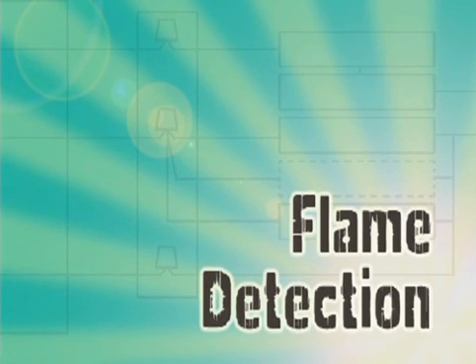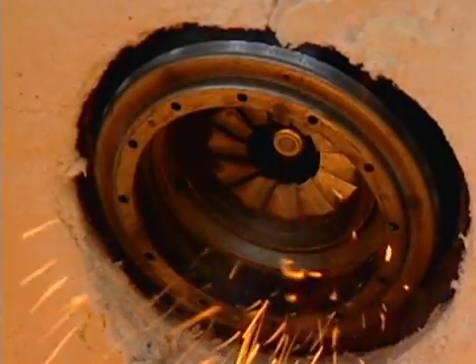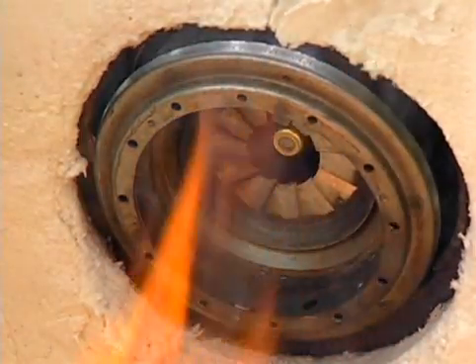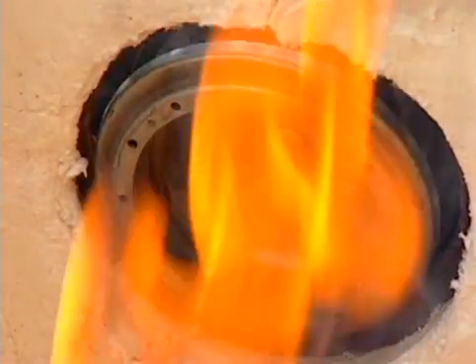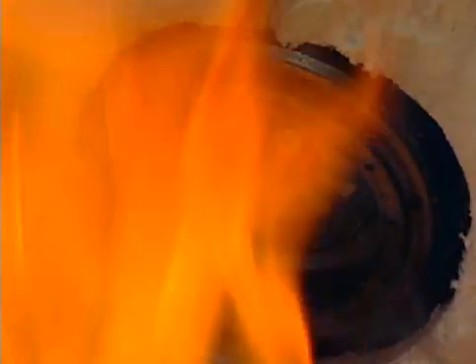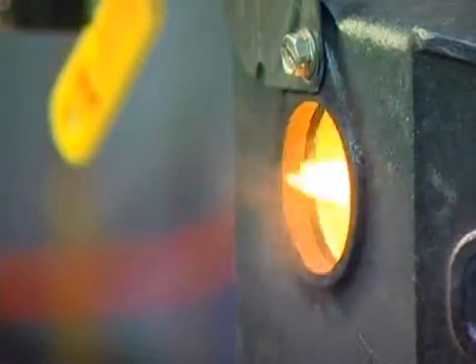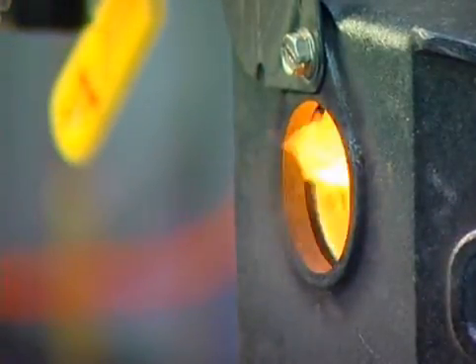Primary controls detect both the presence and absence of flame. A safety feature of primary controls is they will not activate the burner for startup if the control senses a flame during the off cycle. This prevents additional oil from being pumped into a unit that already has a fire burning before startup.